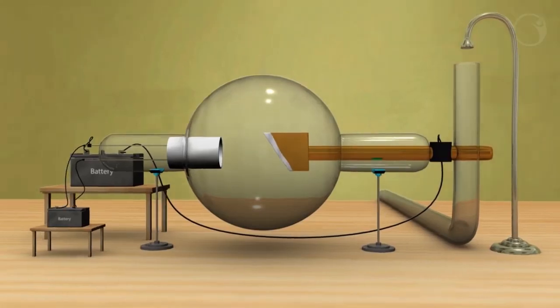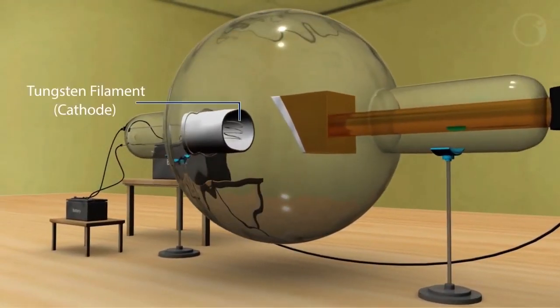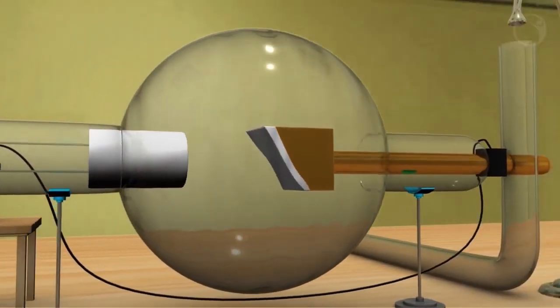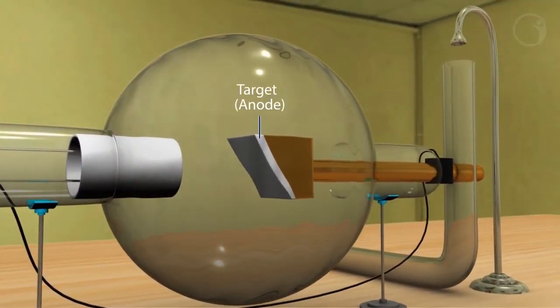It contains a highly evacuated glass bulb containing a cathode, which is a tungsten filament, and an anode, which is a target made up of metal of high atomic weight.